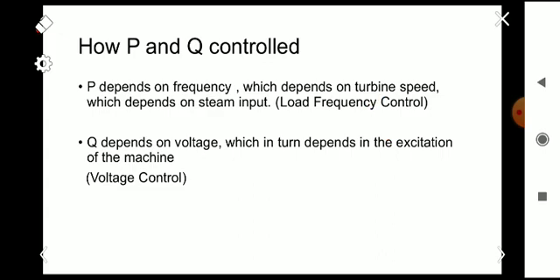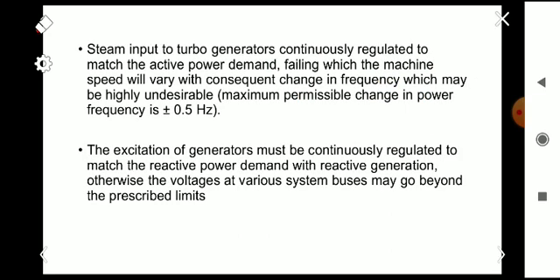So we have two controls here: controlling the input to the machine is called Load Frequency Control, and controlling the excitation of the machine is Voltage Control. In Load Frequency Control, we are maintaining the frequency as constant — the steam input to the turbo generator is continuously regulated to match the active power demand. Normally we keep the frequency of the power system at 50 Hz, and the permissible change in power frequency is plus or minus 0.5 Hz, that is between 49.5 and 50.5 Hz.